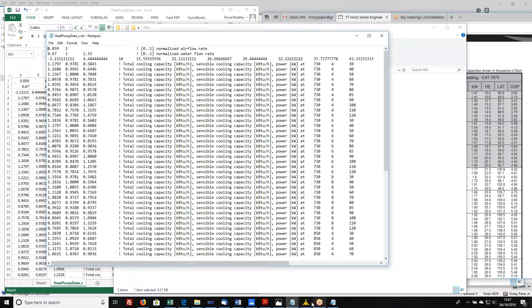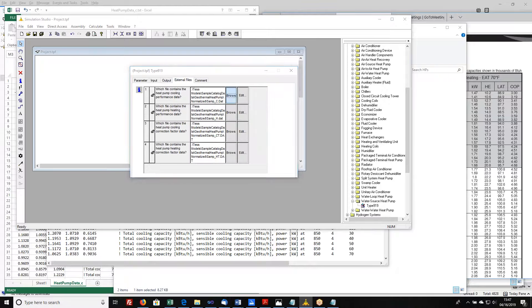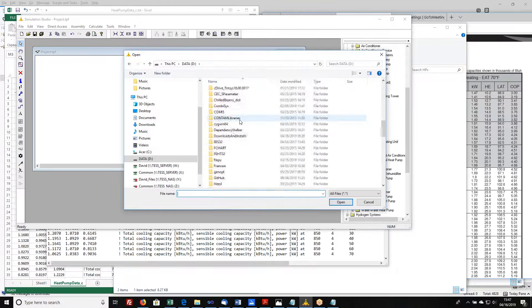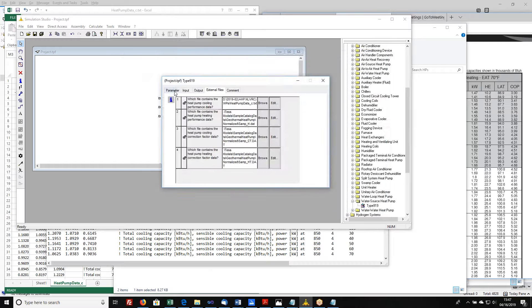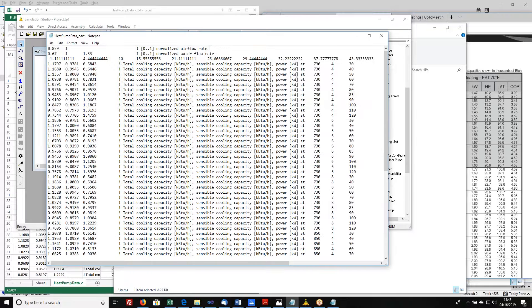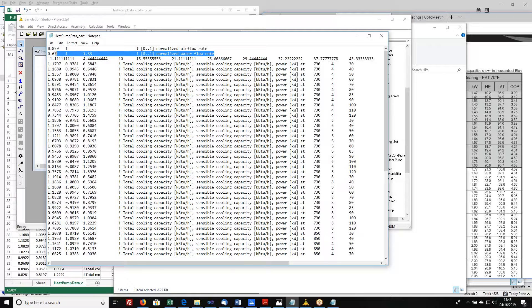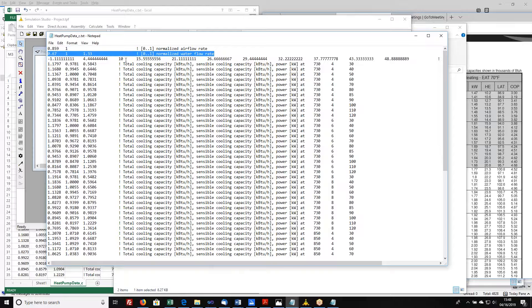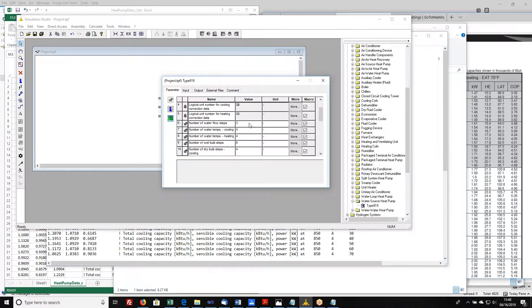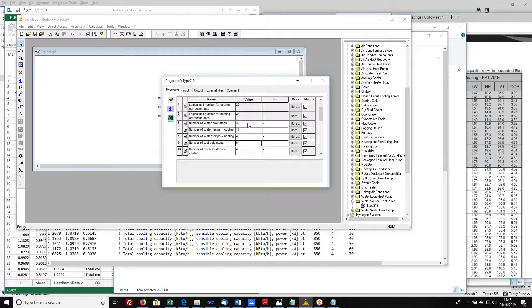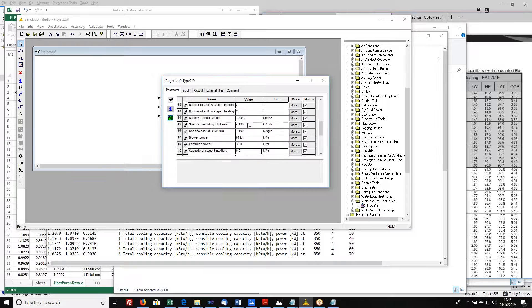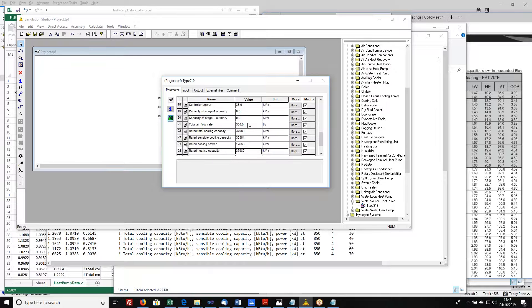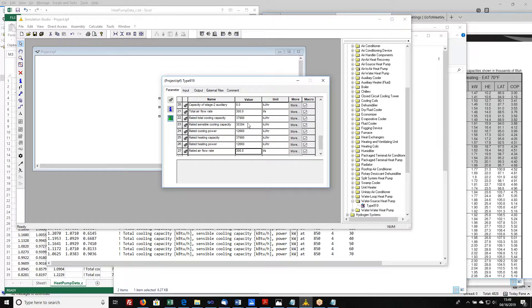All I have to do now is point this to my new data file. Now, you have to make sure that these parameter values here match what's in the data file. Remember, we didn't change the number of air flow rates and we didn't change the number of water flow rates, but we did change the number of entering water temperatures. So we've got to make sure that that's reflected. So we've got 11 values of entering water temperature. So I need to go down here. I still have three water flow steps. But here where it says number of water temperatures in the cooling file, I've got to make that 11. Likewise, I'd have to go down through the rest of these with the other two data files as well. The final thing that we have to do is to go down here and make sure that these bottom parameters reflect the values at the rated condition. These values are going to be multiplied by the multipliers in the data file. That is what's going to give us the actual performance of the machine.